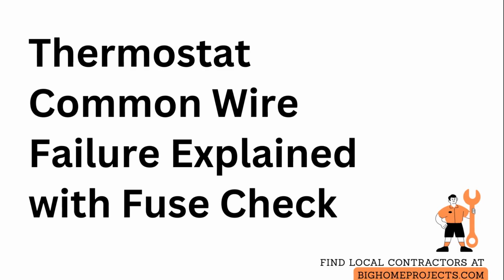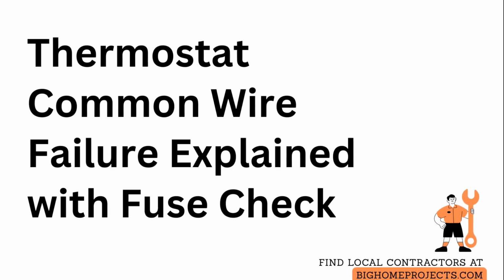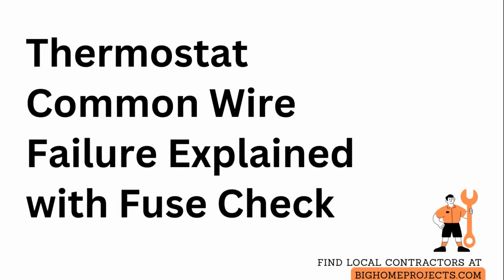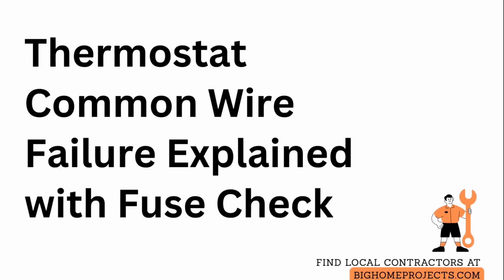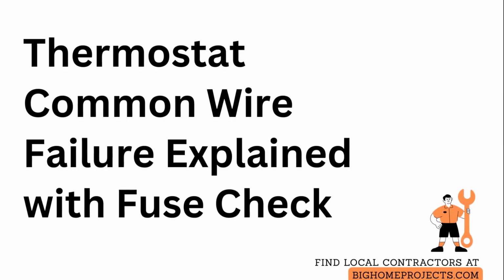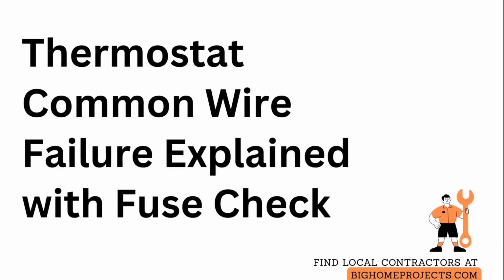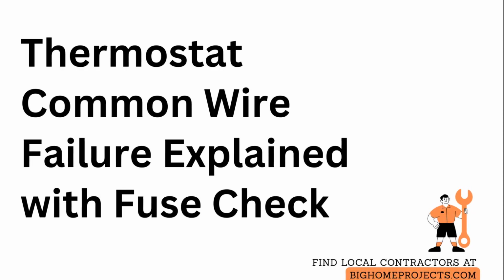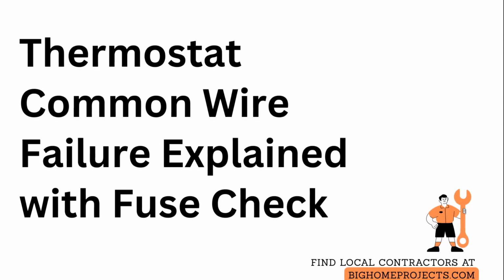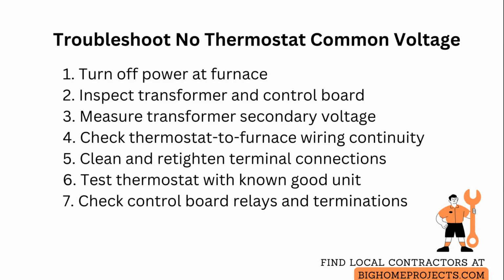If a thermostat calls for heating or cooling and there is no voltage between the common and the appropriate terminal, that missing signal usually points to wiring, thermostat, fuse, or transformer issues that need immediate systematic checking. First, turn off power at the furnace or air handler to avoid shorts.